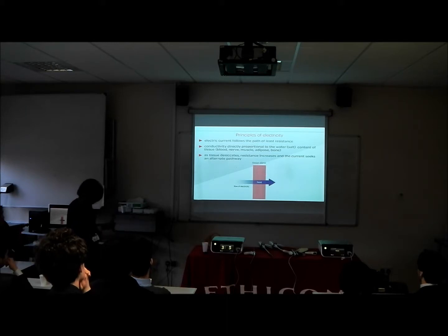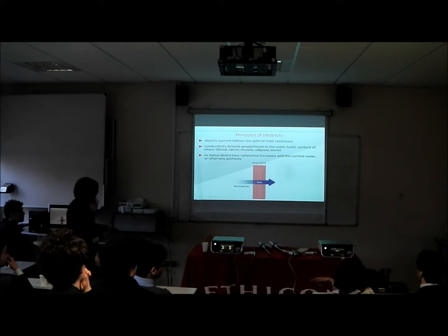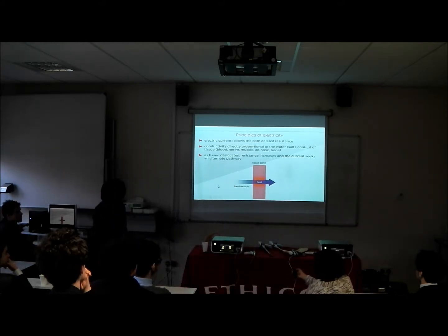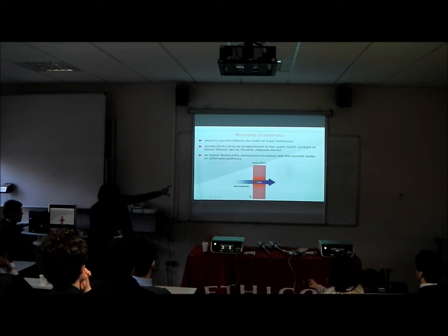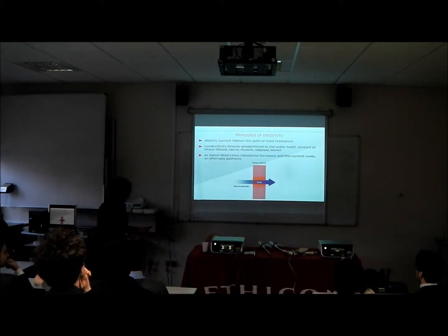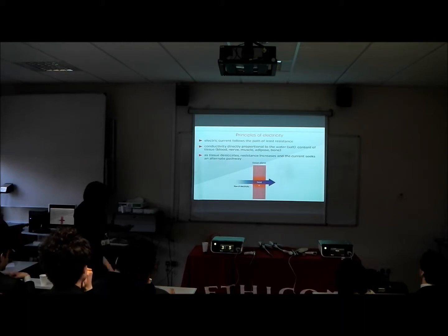So if you look at that, okay, play it. So can you see how the redness has increased? So basically the heat has spread. So if you can see the spread of the heat, when we started, we wanted only this area to be burnt, or coagulated, or cut. Now if we continue using the electric current, this is where it has gone to.